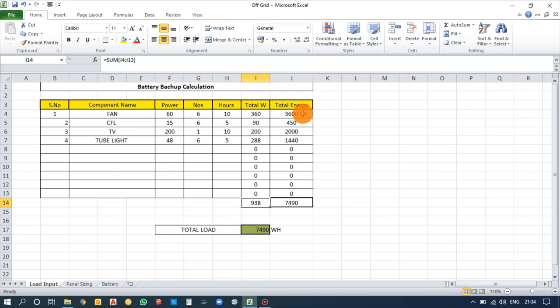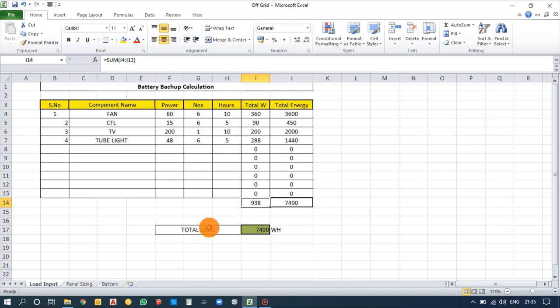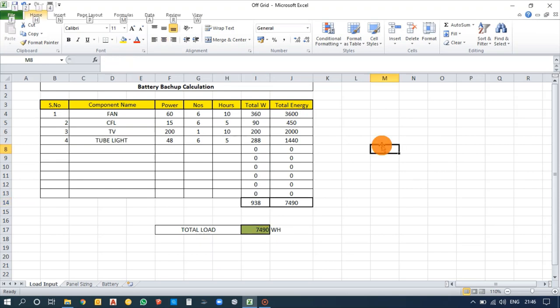For total energy in watt-hours, multiply the total watt by the number of hours each component will be used. I am getting 7,490 watt-hours, so the total load is 7,490 Wh. This is the basic calculation from your load estimation.